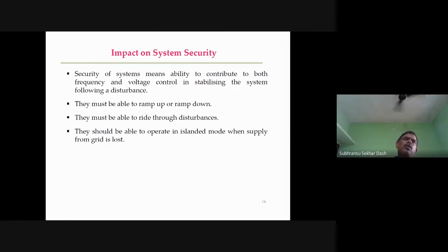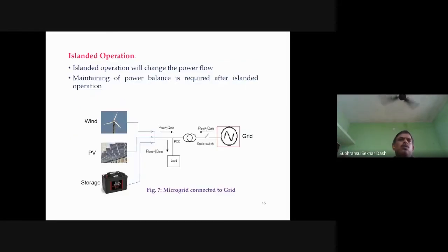You understand? So they must be able to operate in island mode also. Island operation will change the power flow, and maintaining the power balance is required after island operation. When you are getting power from the grid, things are different. When the grid is not supplying power, there is a problem in the grid or your system has a problem, you work as an island system. So when you work as an island system, your power management will be different. When the grid is connected, the power management system is different. When you island, your power management will be different.